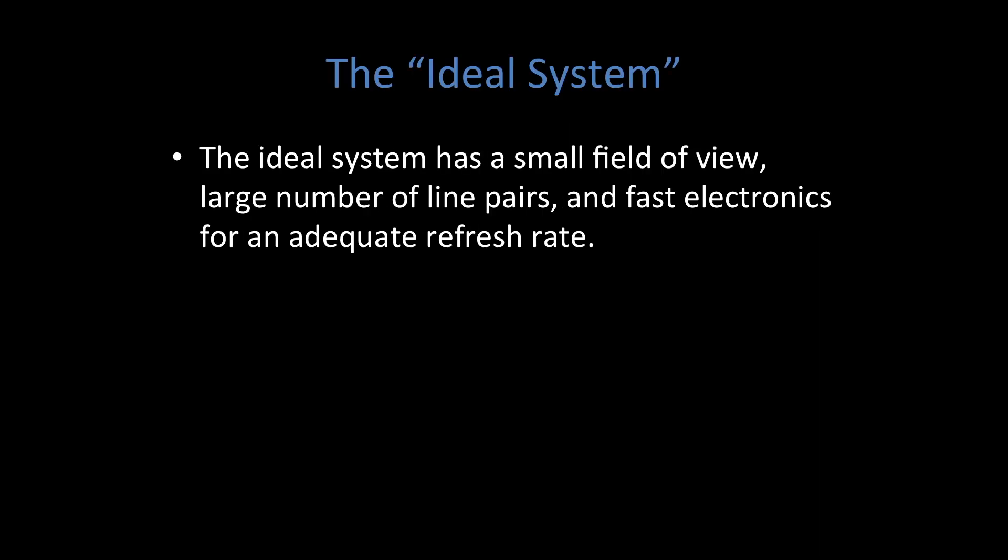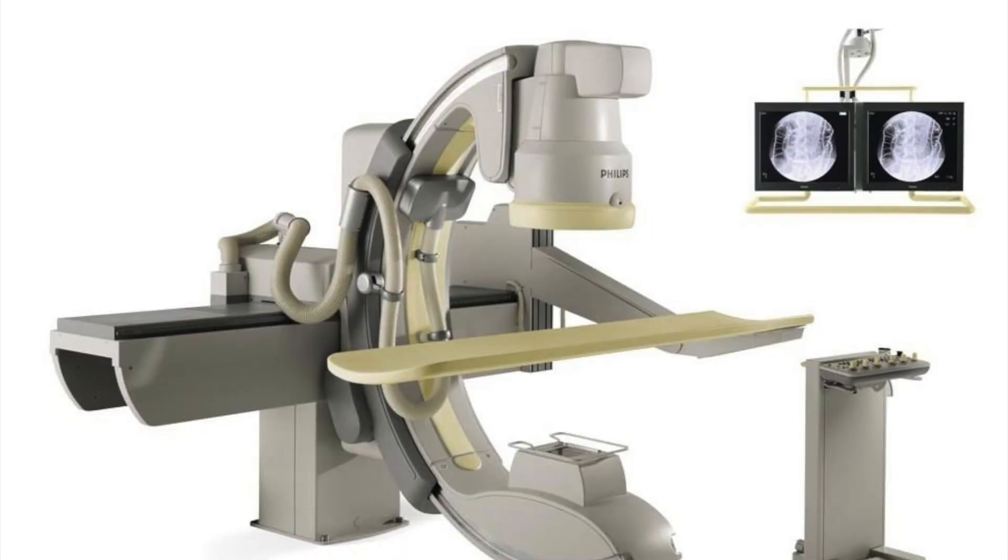Finally, I wanted to talk about the ideal system. The ideal system in theory would have a very small field of view, a large number of line pairs — improving your resolution — and fast electronics, which means an adequate refresh rate. Remember, this system is used for fluoroscopy, therefore we want to image in real time. We do want high resolution but we cannot limit our frames per second in order to achieve a super high resolution.